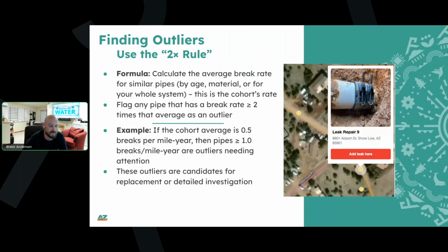And it's like 100x more than the industry average, which is 1 break per 10 miles. And so at this point, we have to start anticipating that we're going to see this problem continue to get worse, not better, because if there's a joint every 20 feet, that means we could be looking at 55 more repairs if we continue patching this problem rather than actually address it.